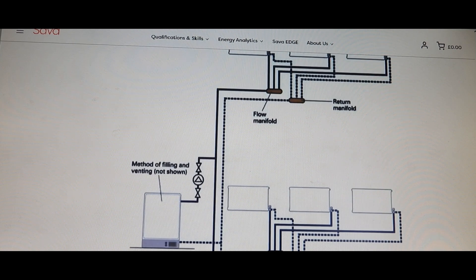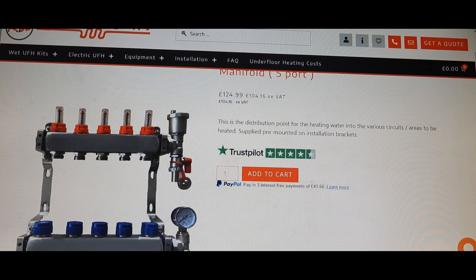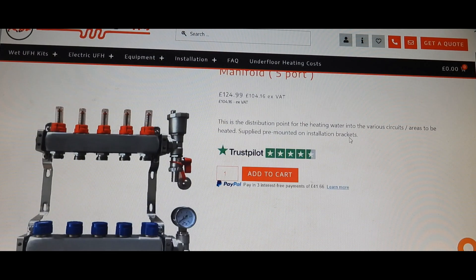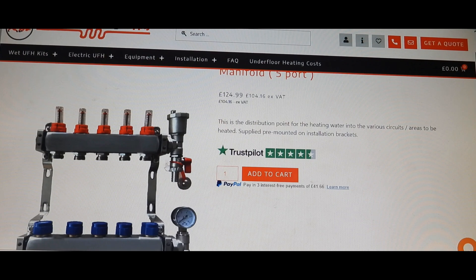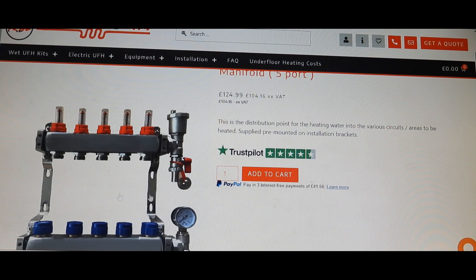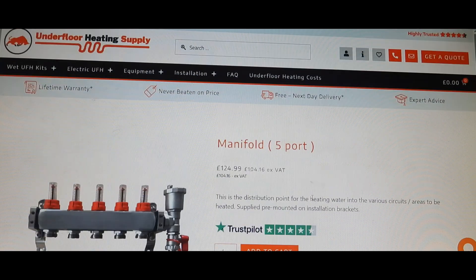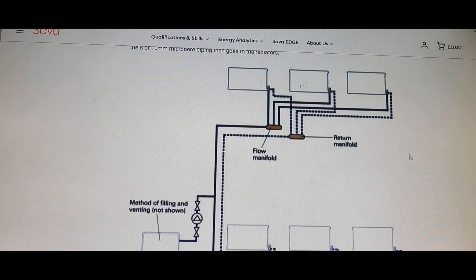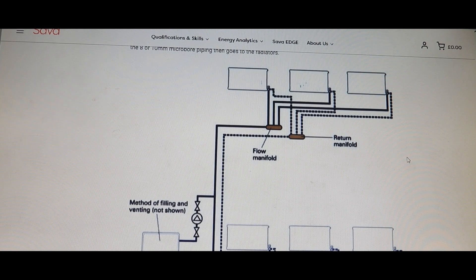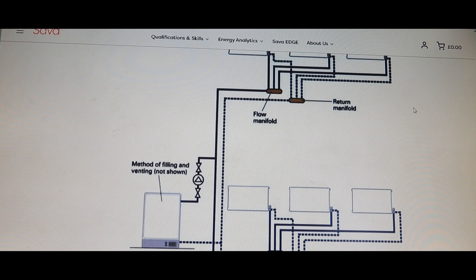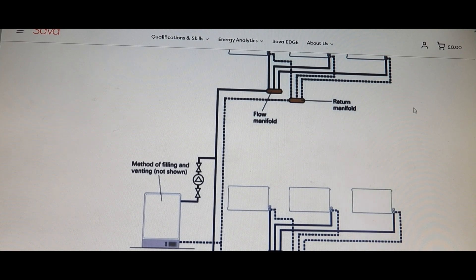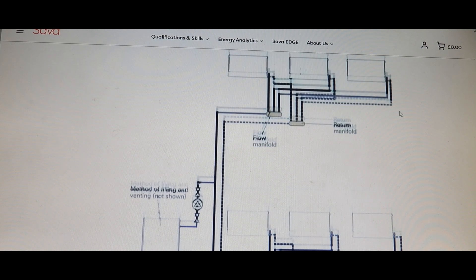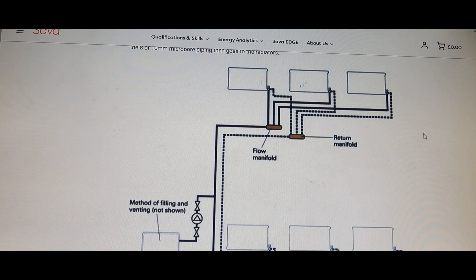By that I mean you can get another manifold like this one, which is a five-port one, and change it onto your flow and return and you've got all these extra ports for rads. Run your actual radiators right back to the manifold. I know it's not what you'd like to hear, but it is the best way to do it. That way you can add your pipe, but just remember that you can't run this microbore pipe too far.